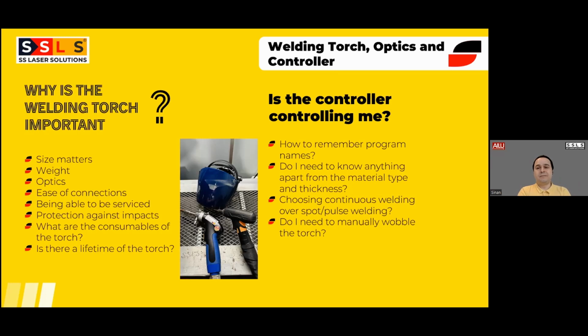Normally, you will not need to buy a torch brand new. There are, of course, some cases, like if you burn the torch or if you run a forklift over it, okay, in that case, you may need to replace it. But it's all the optics, you know, we have the protection lens, focusing lens, reflective mirror, and the collimation lens. So when these optics are changed in time and the internal head is clean from contamination, your machine will work fine on the torch side.